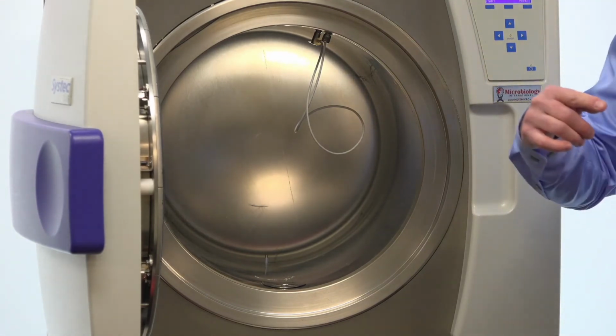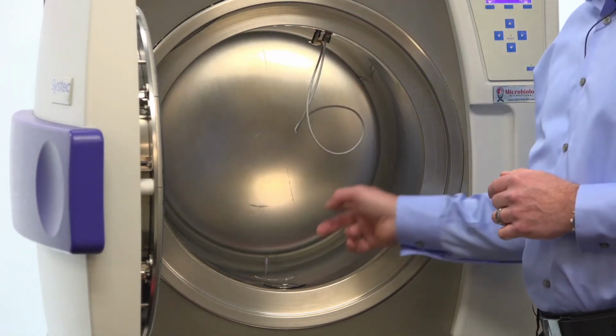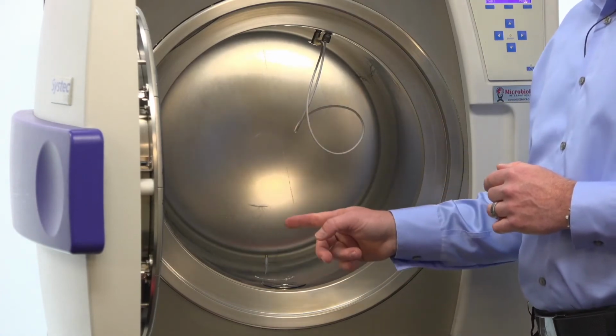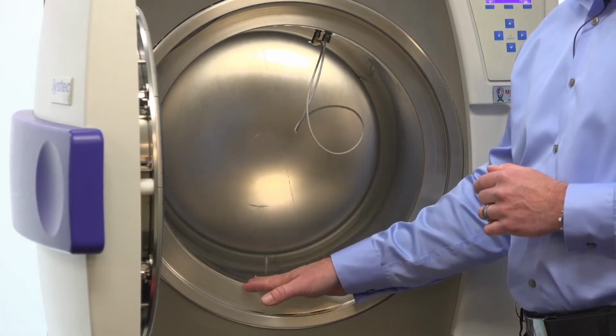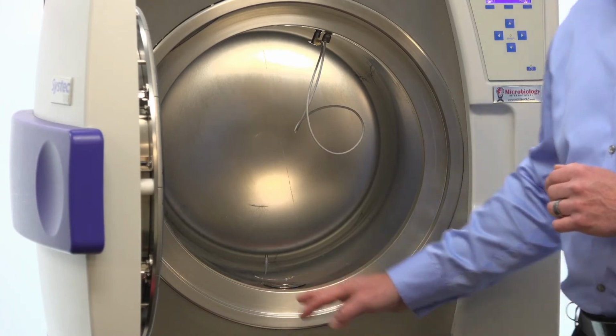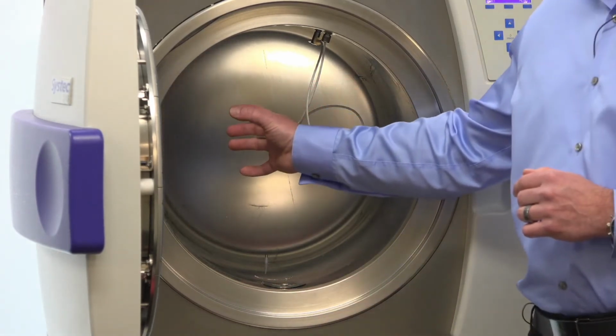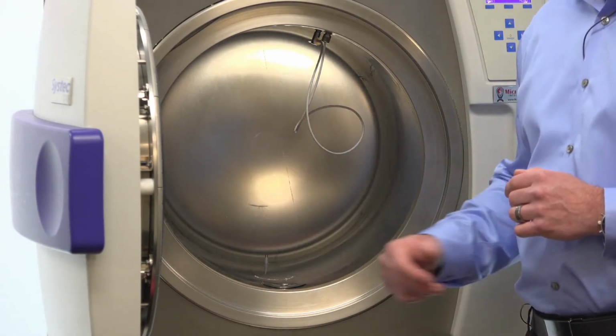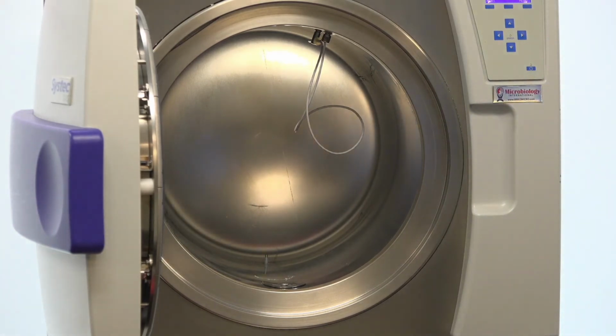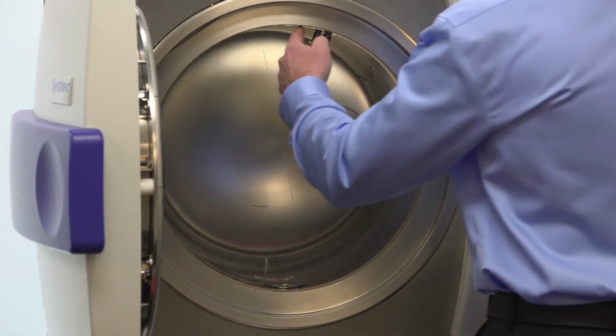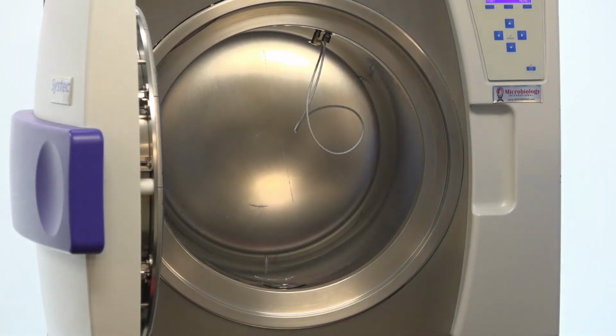So what it will do is run circular until the instrument is completely full of steam, pressing out the air inside of the unit. The reason we do it that way is in case you have anything that could be potentially affected by having steam directly sprayed on it when it is more like room temperature. We don't want to heat it too fast. We do have that shielded steam vent that's just going to run that around.